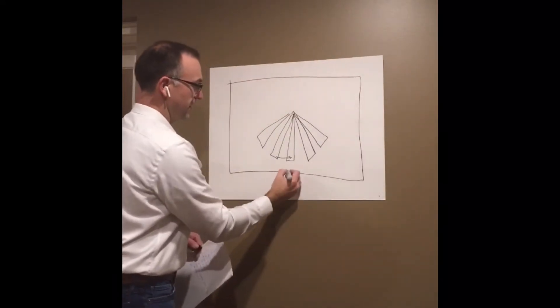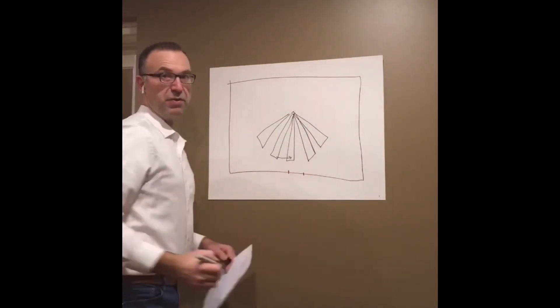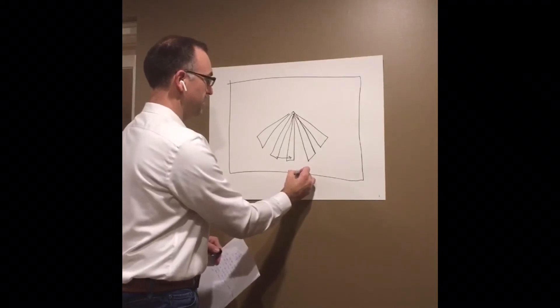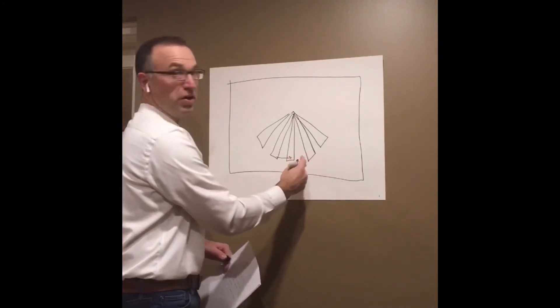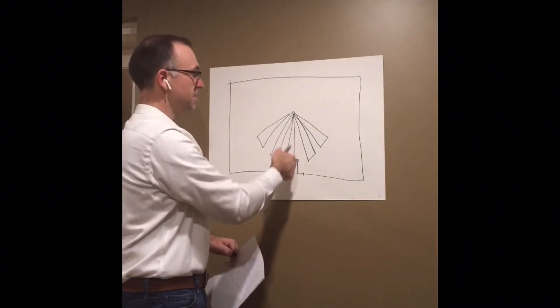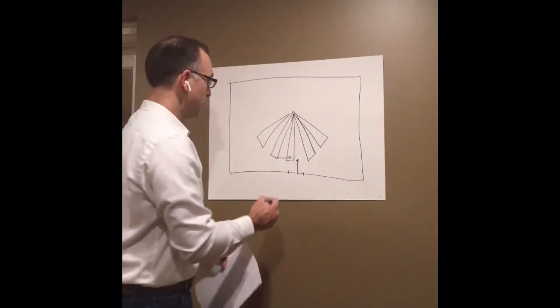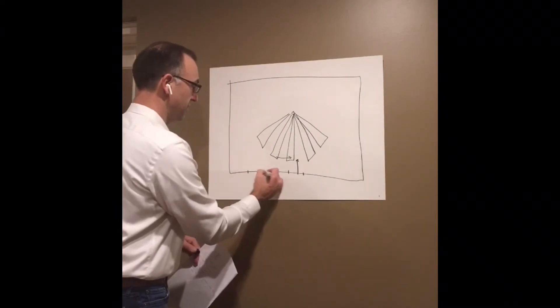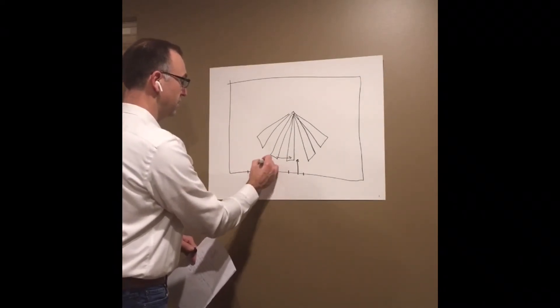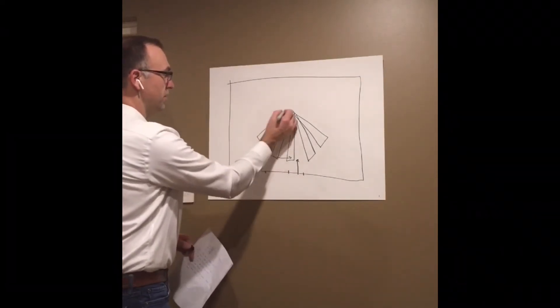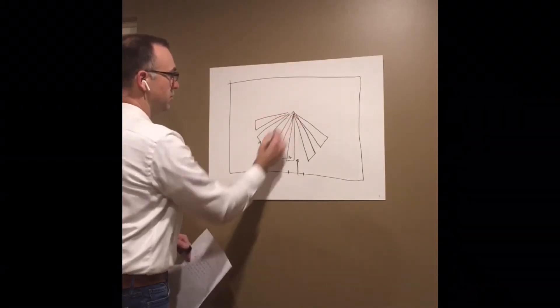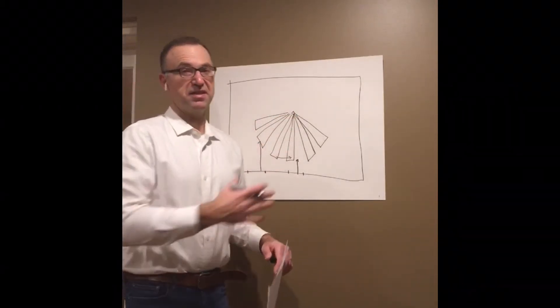And the reason, that's our room and this is our door. If we walk into the room and we walk in this direction, we're actually walking parallel to the sensing zones. And because of that, it may take a few moments for the sensor to pick us up. Where if we had the door over here, we walk in moving this direction, we're starting to go perpendicular to the sensing technology, especially if you had one like this.